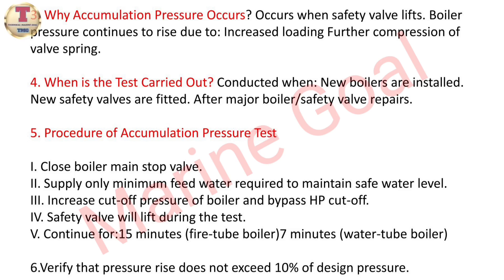Step two — supply only the minimum feed water required to maintain a safe water level. Step three — increase the cutoff pressure of the boiler and bypass the HP cutoff so the safety valve will lift during the test. Step four — continue for 15 minutes for fire tube boilers or 7 minutes for water tube boilers. Step five — verify that pressure rise does not exceed 10 percent of design pressure.